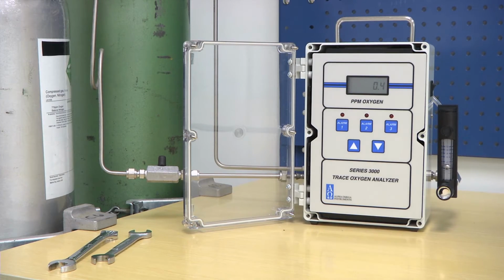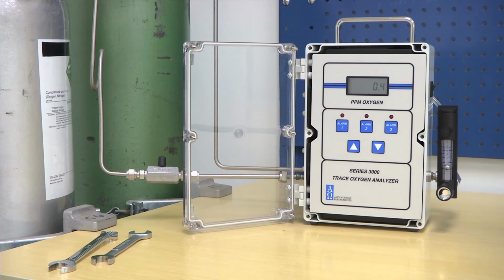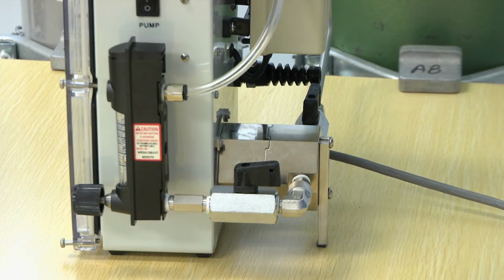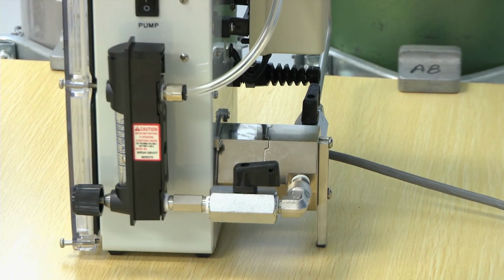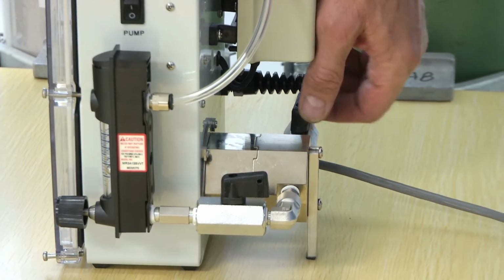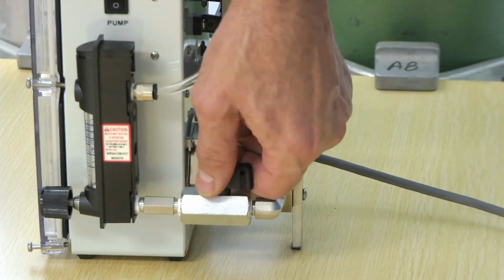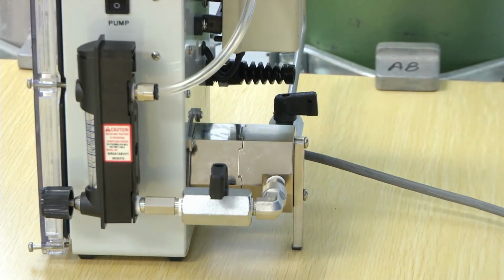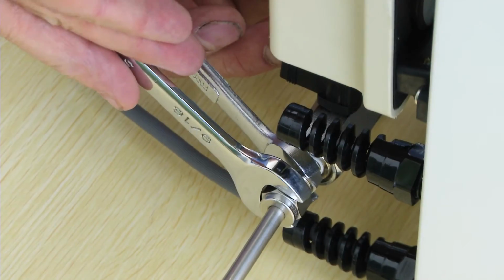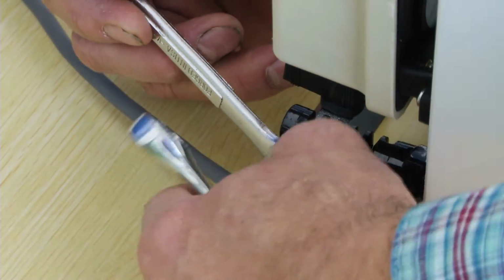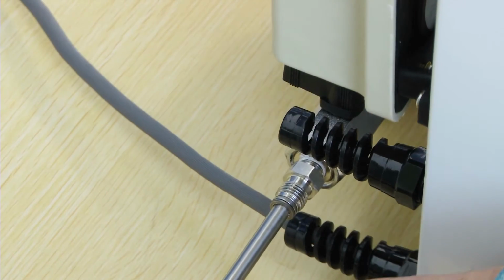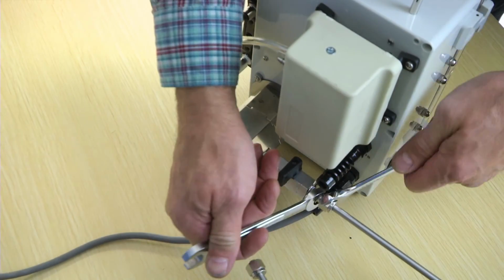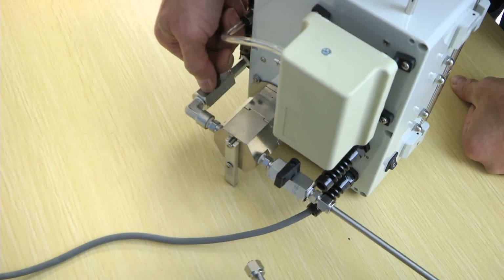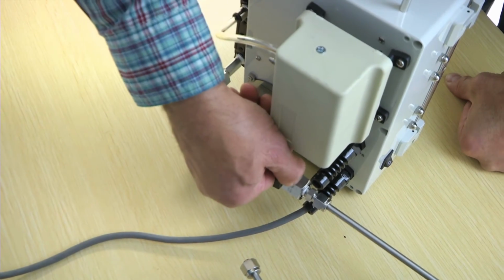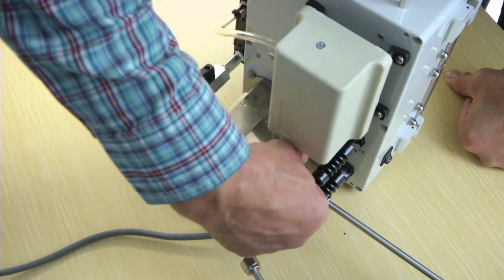Once you are convinced that the sample delivery systems are free of air leaks, it's time to connect the calibration gas for the final steps in the process. Please keep the isolation valves closed whenever you're changing the sample gas feed to the analyzer. As you can see, I am closing the valves in anticipation of connecting my calibration gas. As I mentioned previously, the calibration gas being used for this demonstration is certified by our supplier of calibration gas to contain 779 ppm of oxygen with the balance of nitrogen.